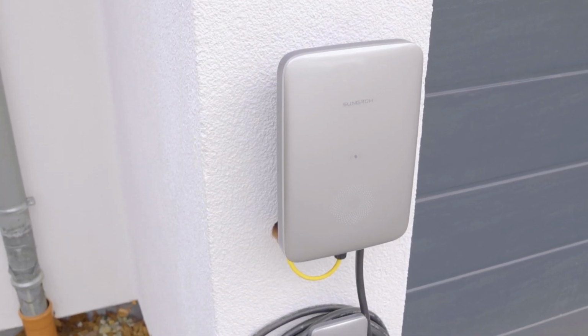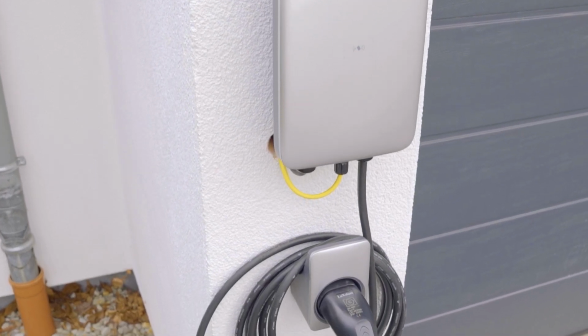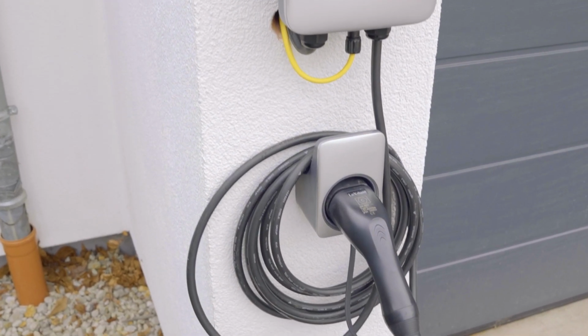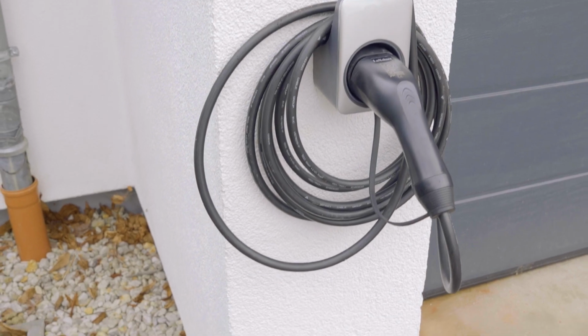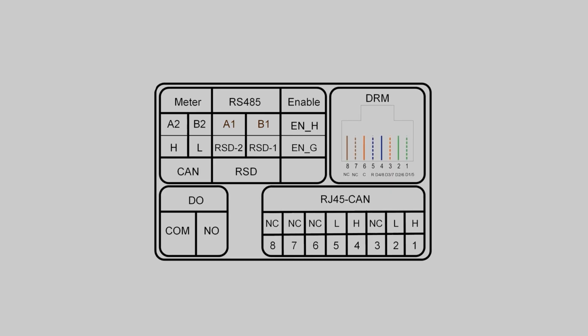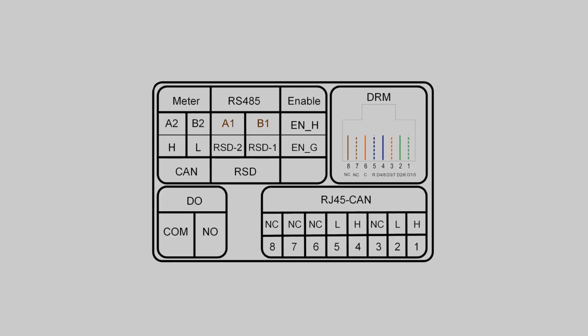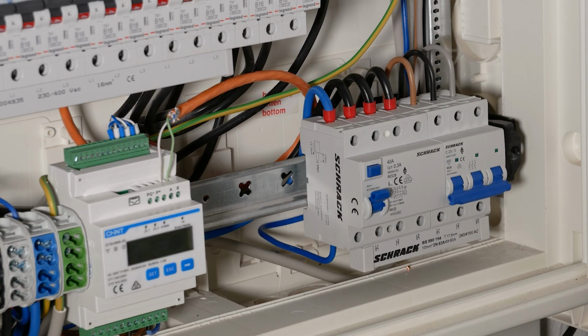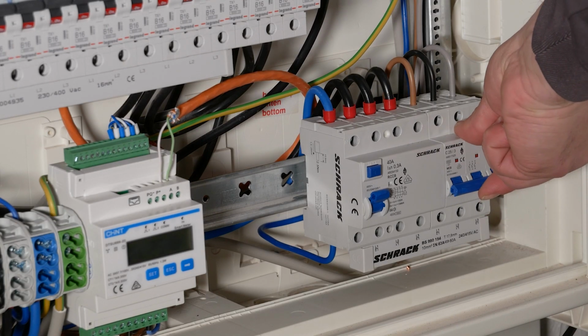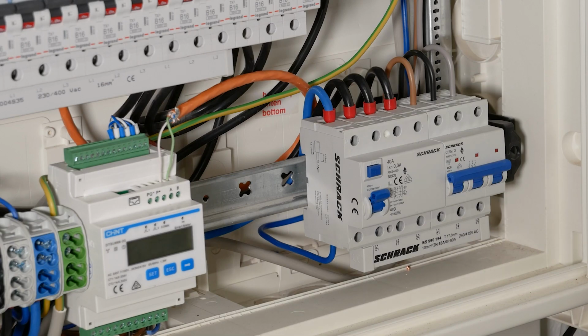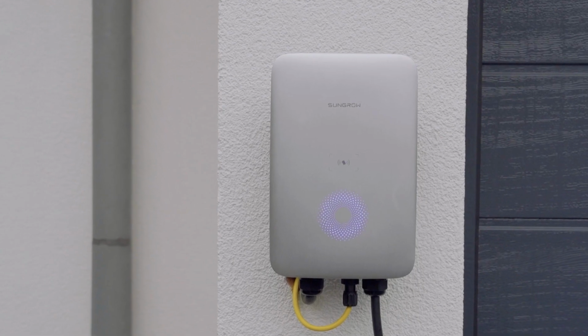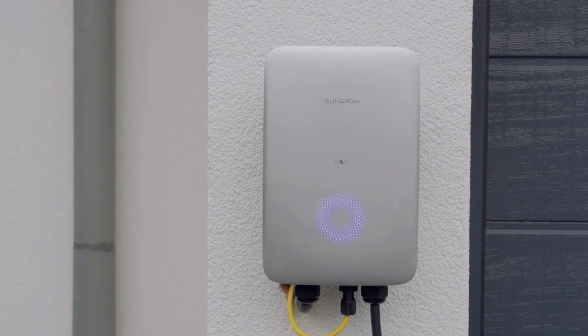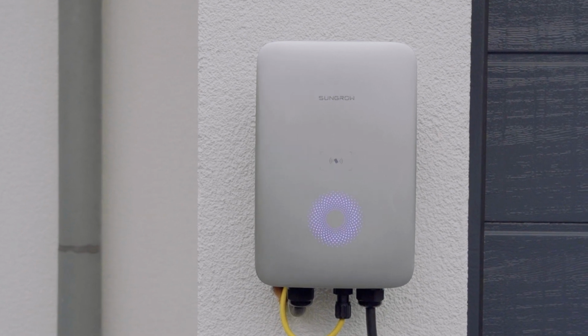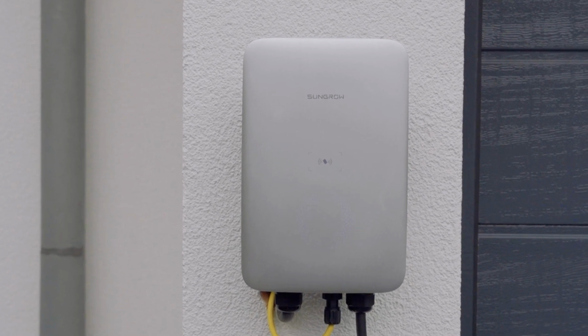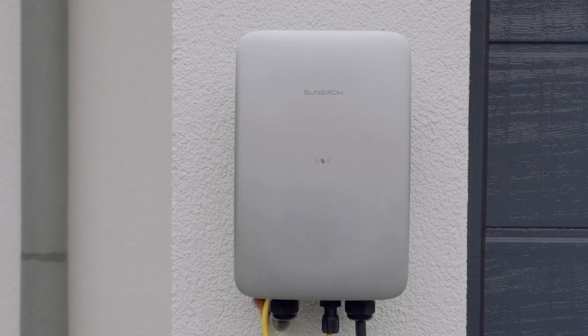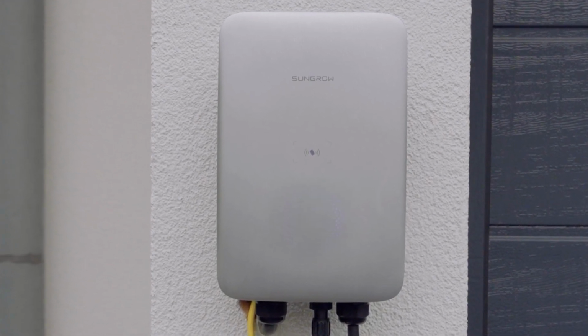If you're installing the 7 kW AC charger in combination with Sungrow's single-phase hybrid inverter, you need to connect the same ports A1 and B1 for the RS485 cable. After the installation is finished, switch on the circuit breaker to power up the AC charger. The blue LED indicator on the charger will start flashing slowly, which indicates the standby status. There are different status descriptions of the LED indicators, which are explained in the user manual.